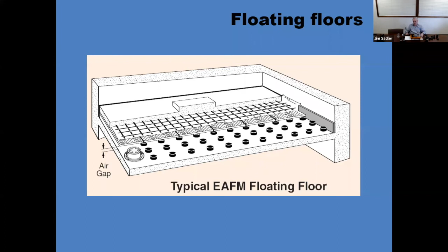So the height of the mounts creates the air gap. But with this system, we're running about 600 millimeters between supports because we're limited by the plywood—the plywood has to be supported, we can't have it sag under the concrete. This is an okay system, but one of the primary weaknesses is that, despite everyone's best efforts, the people who pour concrete are generally not ballerinas. They're up there with hoses and rakes, pouring this concrete as quickly as they can, and sometimes concrete gets through the plastic into one of these gaps and creates a stalactite across the air gap. We've had this happen to us, and it short circuits the entire floor.